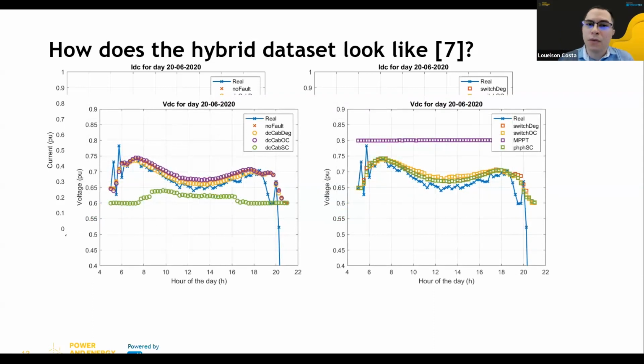Then we start to take a look at the DC link voltage. We measure the DC link voltage for those multiple conditions, and in this case, the DC cable short circuit is easily distinguished as it was on the current, and it may help a little more to distinguish the switch degradation. For the MPPT fault it's very easy to distinguish from the DC link voltage.